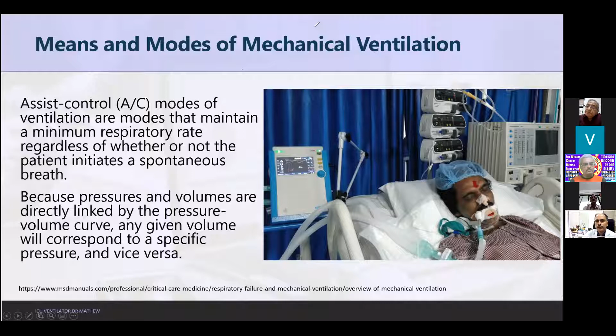Then we have the adjustable ventilator settings. There are a lot of settings which can be adjusted for different things, like the respiratory rate, the tidal volume, and the trigger sensitivity. Trigger sensitivity basically means that if a patient is breathing and trying to take a deep breath, we set a trigger so that when the patient's inspiratory effort goes to -2 centimeters of water, the ventilator will then send the air inside. So the ventilators can also be selected to have a trigger.